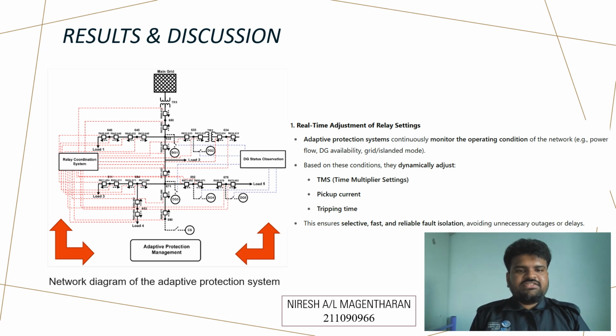So the figure shows network diagram of the adaptive protection system. So real-time adjustment of relay settings. Adaptive protection systems continuously monitor the operating condition of the network. Example, power flow, DG availability, grid and islanded mode. Based on these conditions, they dynamically adjust TMS, which is time multiplier settings, pickup current, tripping time, and this ensures selectively fast and reliable fault isolation, avoiding unnecessary outages or delays.